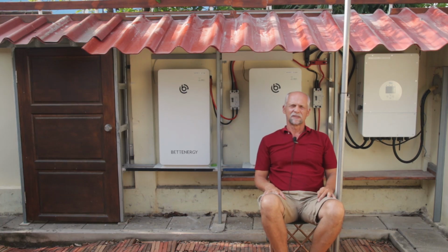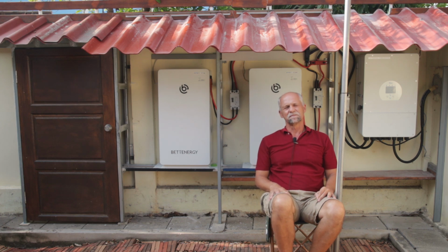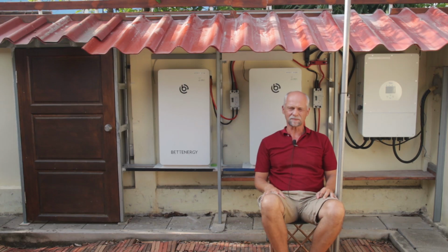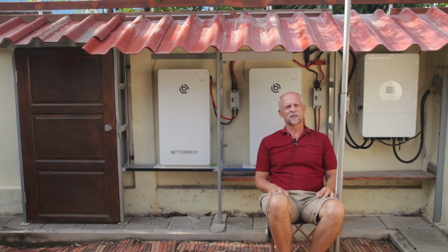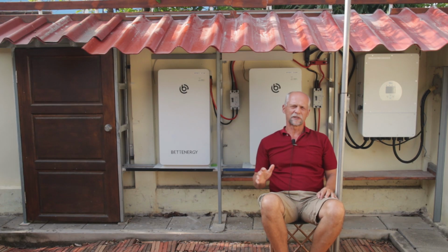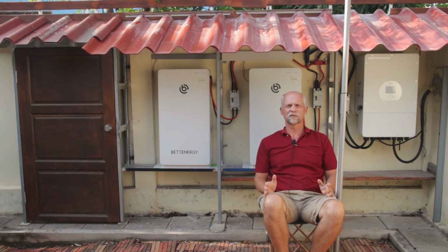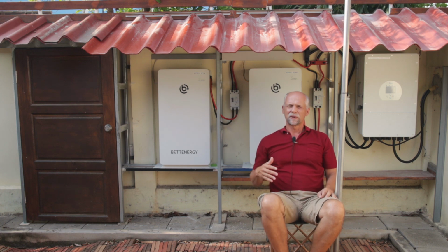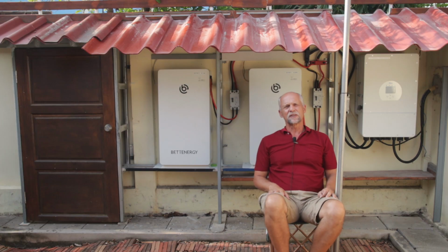Another important change I had to make was in the system work mode, on page 2, for time of use, and there I totally changed the battery strategy. With my old battery, it was actually too small for my PV system, so there was no issue charging it almost every day. But with a bigger battery, you have to make sure it's also, from time to time, charged up completely.